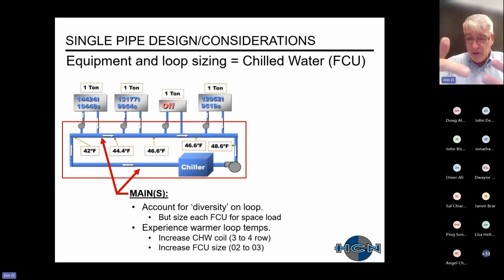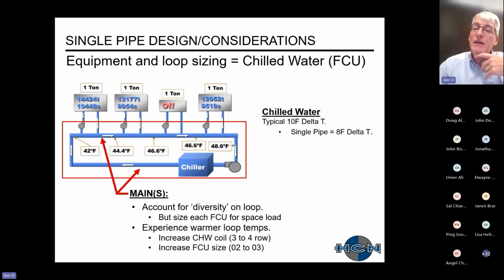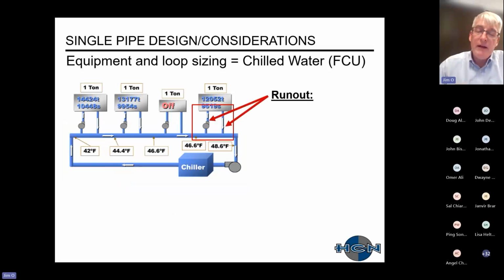As an example, a size 2 fan coil is probably the same size as a number 3. So while the cabinet, the fan, et cetera, stay the same, they just put a couple extra fins or a slightly larger face area on the coil. So usually it's a very small add to increase the capacity of your chilled water coils. Typical chilled water delta T, I'll say, is 10 degrees. I know that has risen in the last couple of years to 12 and 14, et cetera, but for a single pipe system, you want to have it around 8 degrees.